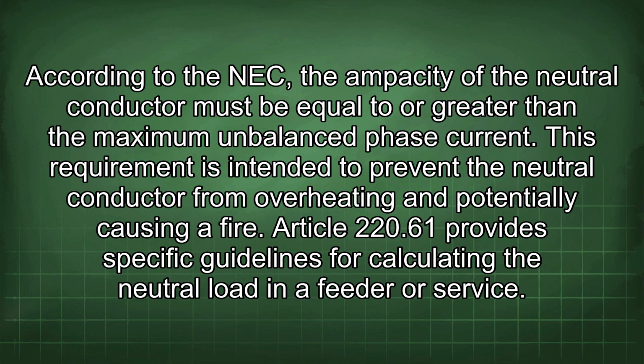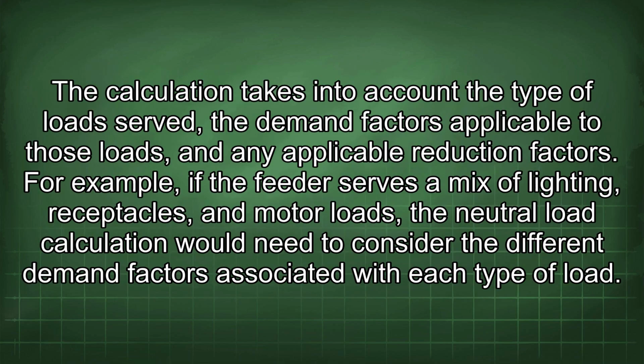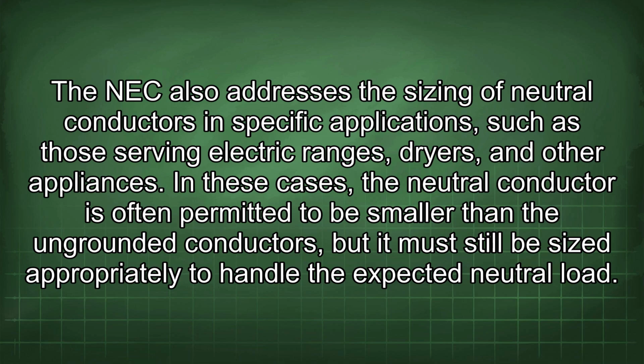Article 220.61 provides specific guidelines for calculating the neutral load in a feeder or service. The calculation takes into account the type of loads served, the demand factors applicable to those loads, and any applicable reduction factors. For example, if the feeder serves a mix of lighting, receptacles, and motor loads, the neutral load calculation would need to consider the different demand factors associated with each type of load. The NEC also addresses the sizing of neutral conductors in specific applications, such as those serving electric ranges, dryers, and other appliances. In these cases, the neutral conductor is often permitted to be smaller than the ungrounded conductors, but it must still be sized appropriately to handle the expected neutral load.